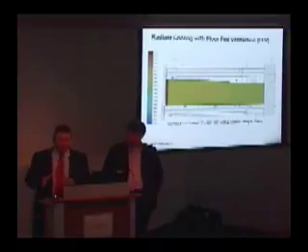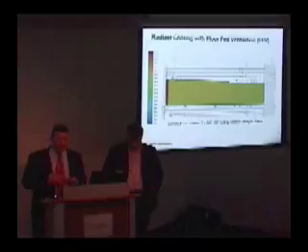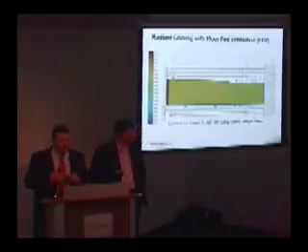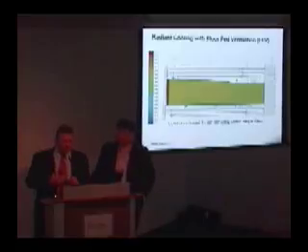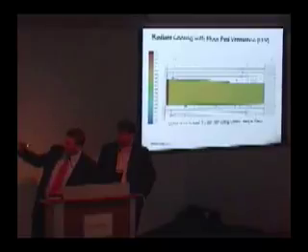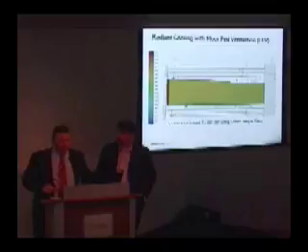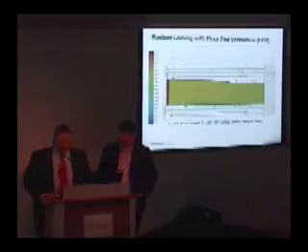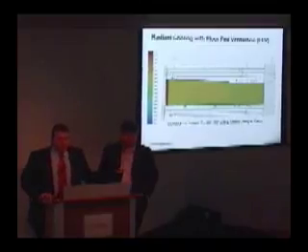Space temperature alone doesn't give enough information. Operative temperature looks at the temperature of the space and also the mean radiant temperature — the effect of radiation on the human body — and combines those two measurements into one metric. In this model, the operative temperature near the core is identical to the operative temperature just within a couple of inches of the exterior wall.